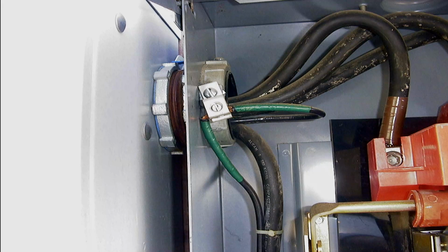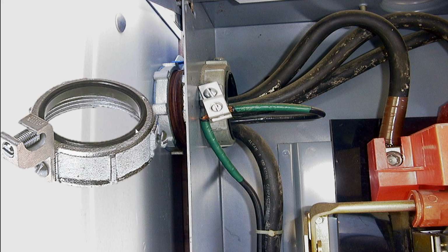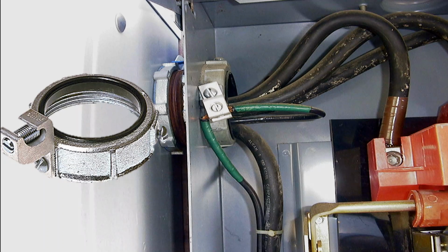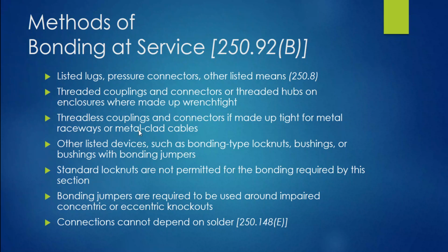This is an example of a bonding bushing with the lug on it, and they're running the connection through it. Okay, here's what they look like. It lays in and it makes connection, and this right here will drive into the screws. All right, methods of bonding at the service, 250.92(B).